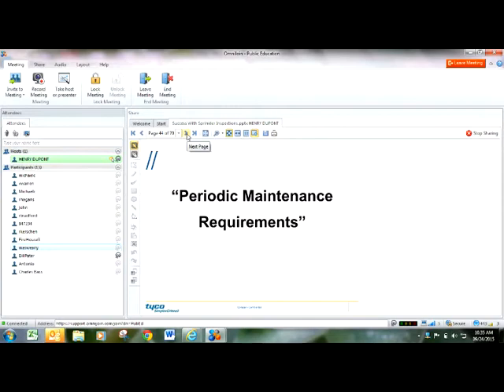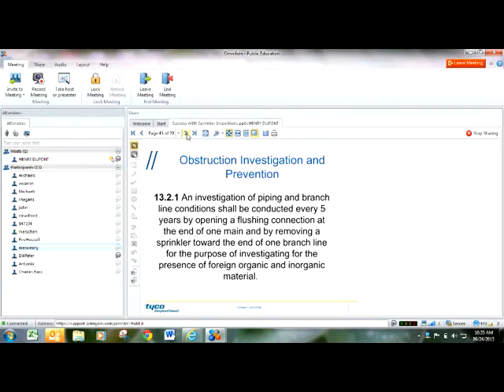Periodic maintenance for fire sprinkler systems. This is kind of a biggie, and I would assume that you guys have all started to look at this: obstruction investigations. Every 5 years, an investigation of piping and branch line conditions shall be conducted by opening a flushing connection at the end of a main and by removing a sprinkler towards the end of the branch line for the investigation of foreign, organic, or inorganic material. Talk a little bit more about that.